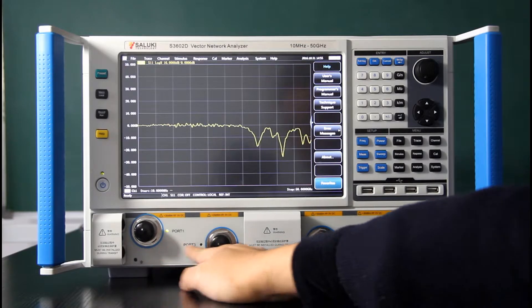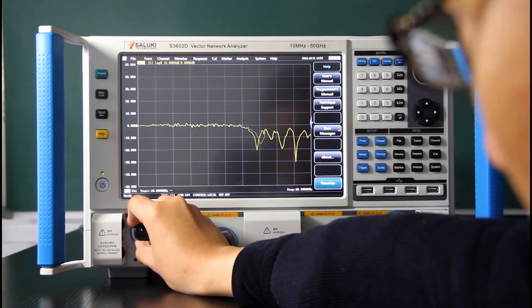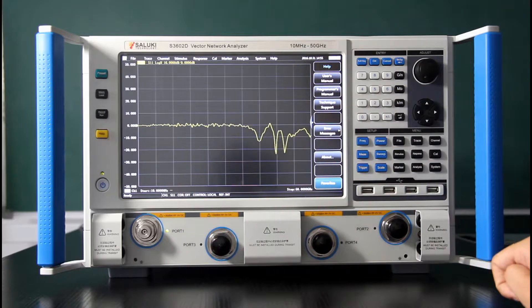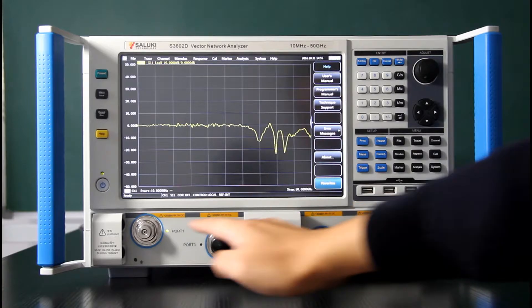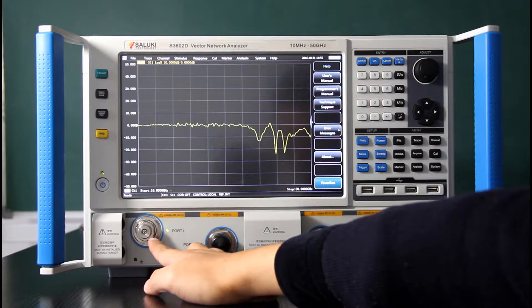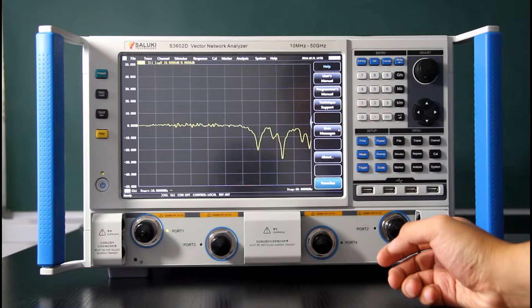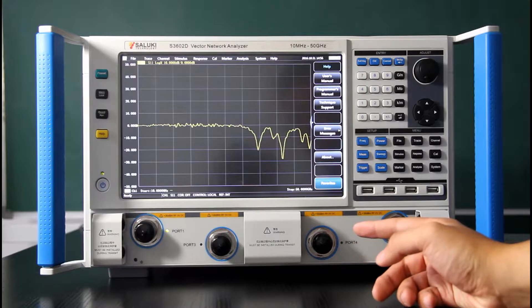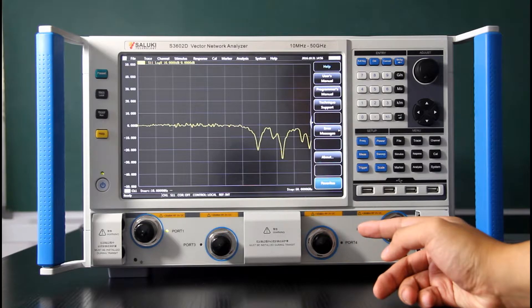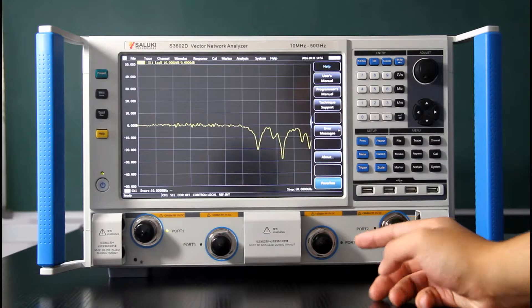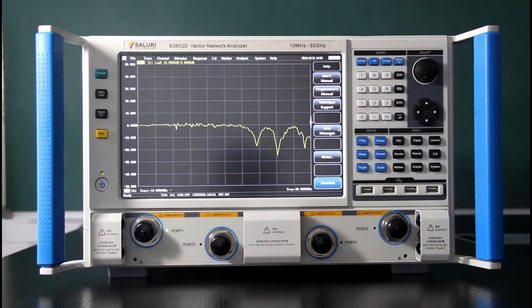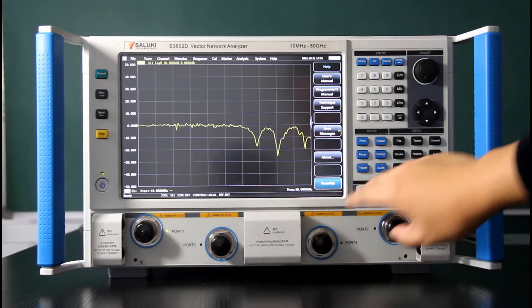Then there are four ports here, four test ports. For this S3602D reaches 50 GHz so the test port here is a 2.4 mm test port. This is not a standard package. The standard package only has two test ports. This has a 400 option which is a four port test. So we have four test ports here. Here are some shields. There are some loops to be protected under it.